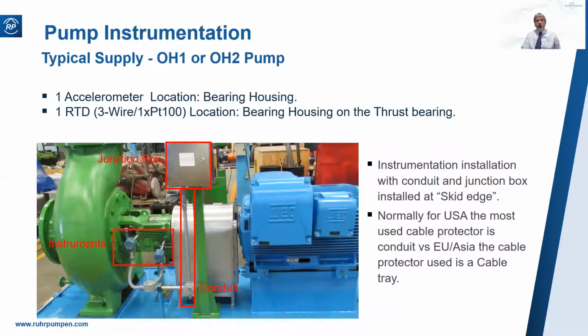Now a few slides to show how the instrumentation is typically installed on various pump types. Here is an OH1 or OH2 pump, 1 accelerometer, 1 RTD, wired to a J-box. And in this instance, the wiring is run in conduit. Now, many customers prefer to see vibration and temperature signals run separately to separate J-boxes, or certainly for them to be segregated within the J-box, so you don't mix millivolt and milliamp signals.